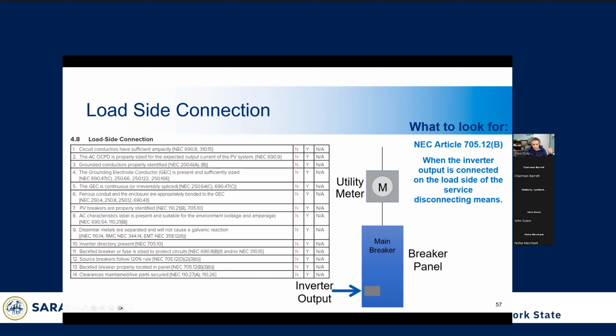And so the thing to keep in mind here is the sum of the backfeed breaker, which is the breaker from the inverter, and the main breaker can't exceed 120% of the bus bar rating. So for instance, if you have 100 amp service coming in and you have 100 amp bus bar rating, you can have a 20 amp backfeed breaker and it'll still be acceptable within the code.